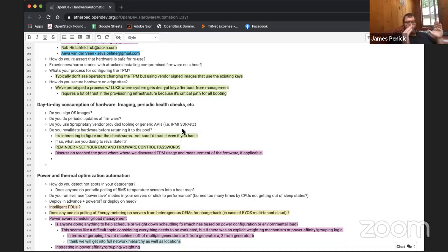The problem is when machines are turned off, then air is blowing the other way. And we talked a little bit about louvers on the backs of machines, sort of like a check valve, so that when the pressure wanted to go the wrong way, it would stop air from going out the front of the machine. But in the long run, building things that way, with a set of shuttered louvers sitting over the back of every machine that would just drop in place and seal if the machine was powered off, ended up being less cost effective, I think, than just turning some of the machines back on.